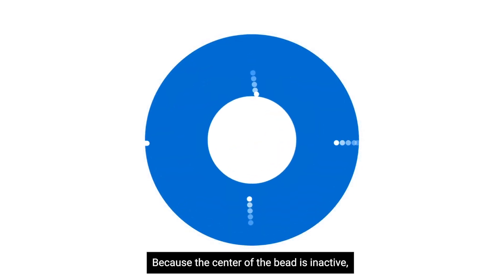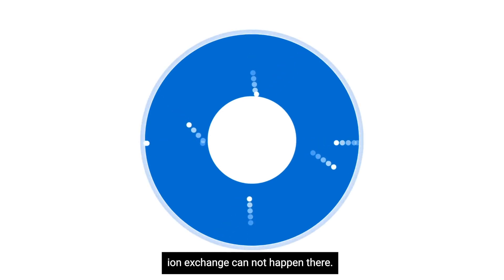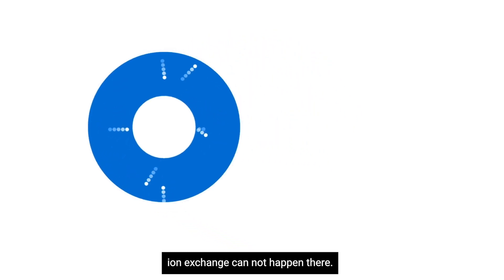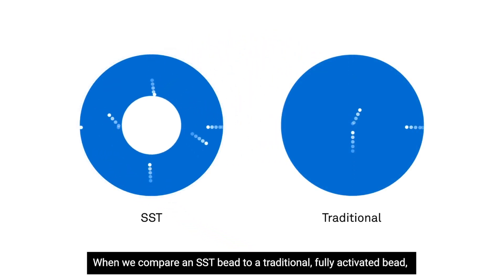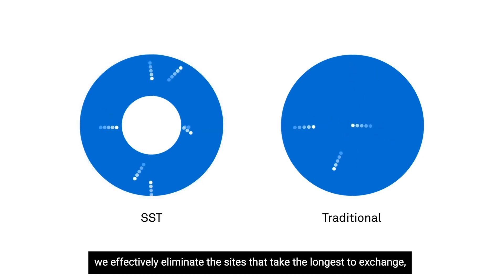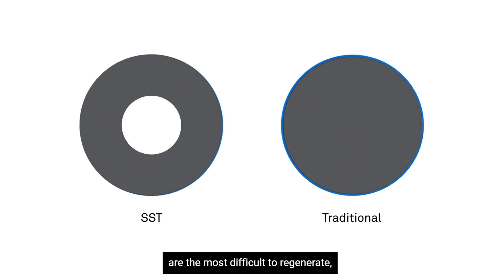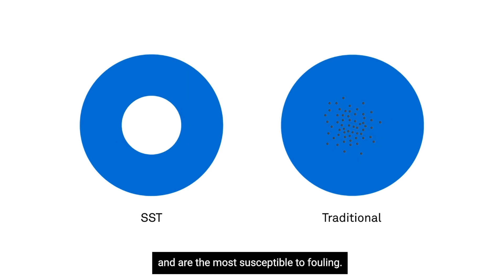Because the center of the bead is inactive, ion exchange cannot happen there. When we compare an SST bead to a traditional, fully activated bead, we effectively eliminate the sites that take the longest to exchange, are the most difficult to regenerate, and are the most susceptible to fouling.